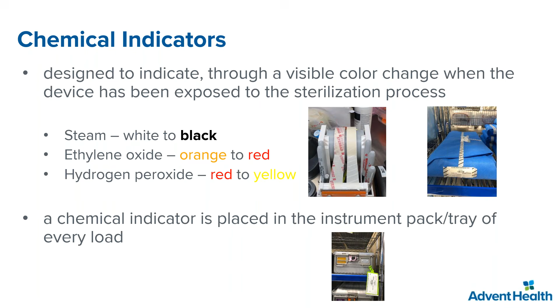Ethylene oxide is another type of sterilization. I don't know how many of you use ethylene oxide, but it changed from orange to red, and hydrogen peroxide changed from red to yellow. I am going to give you the example of all those types of sterilization in a brief moment. A chemical indicator is placed in the instrument pack or tray at every load.